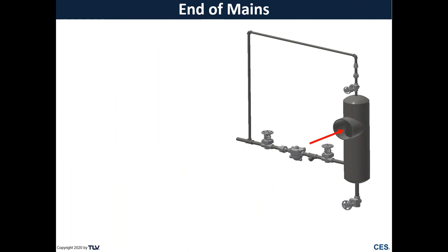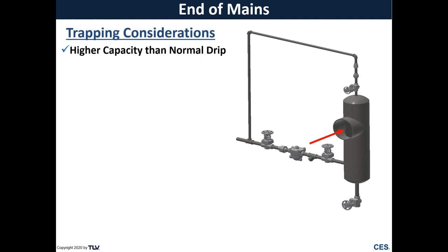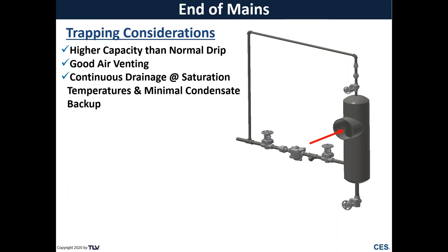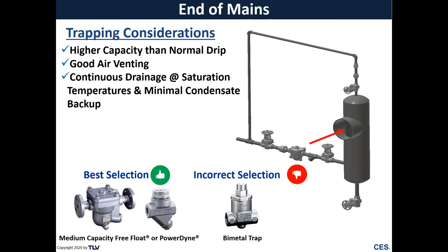So for this, we're typically going to want to have a higher capacity than a normal drip trap, along with something that has good air venting or even adds supplemental air venting. So our best selections for this will be a slightly higher capacity free flow trap or thermodynamic trap. And again, this is not the type of application we would want a bimetallic steam trap on.